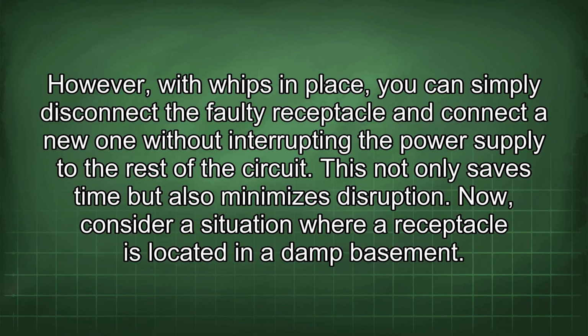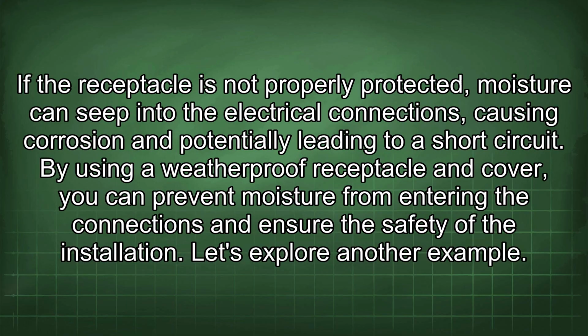Now consider a situation where a receptacle is located in a damp basement. If the receptacle is not properly protected, moisture can seep into the electrical connections, causing corrosion and potentially leading to a short circuit. By using a weatherproof receptacle and cover, you can prevent moisture from entering the connections and ensure the safety of the installation.